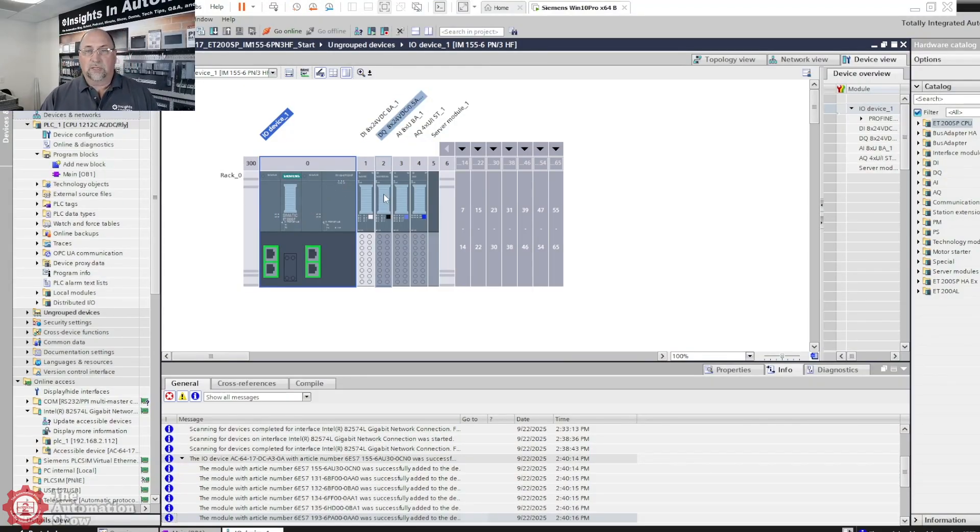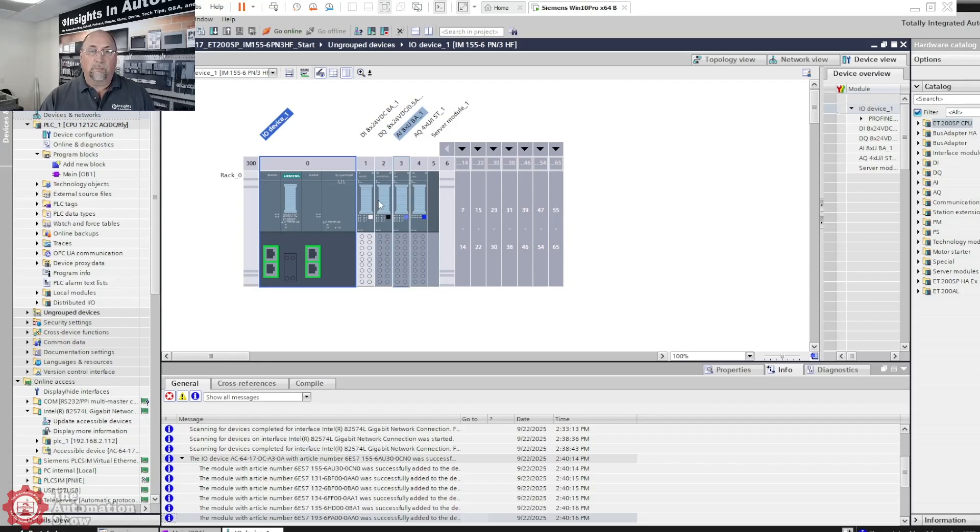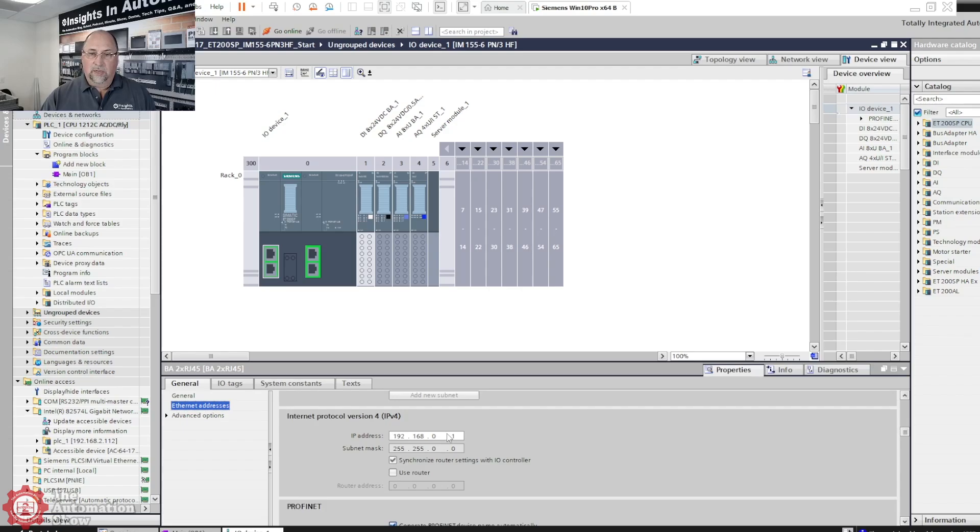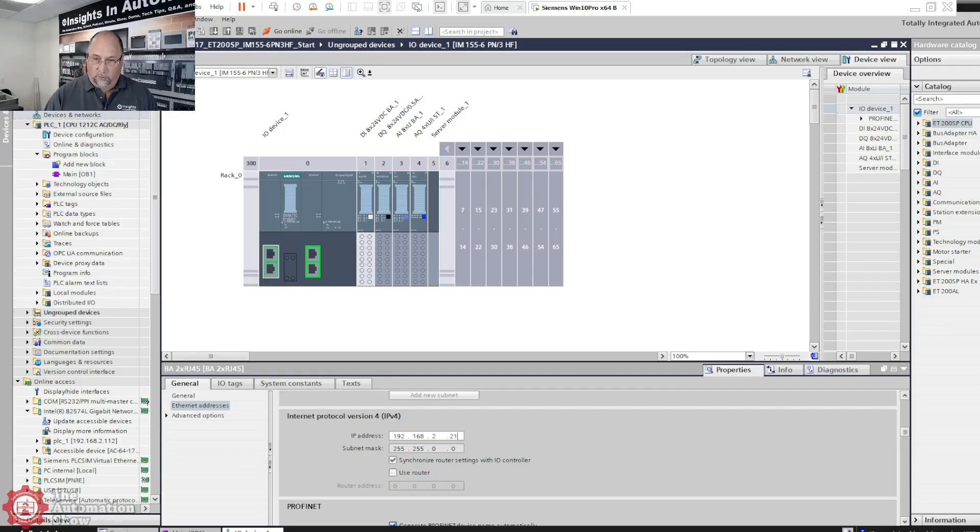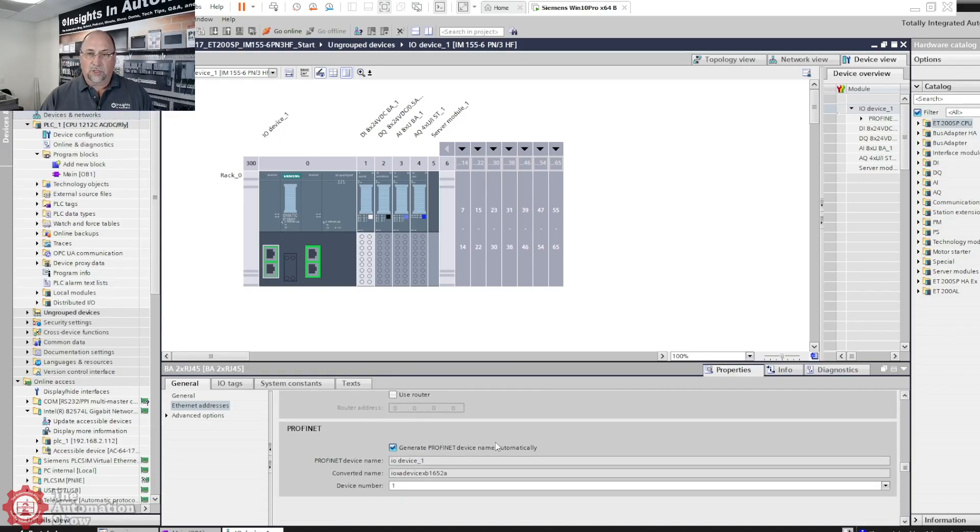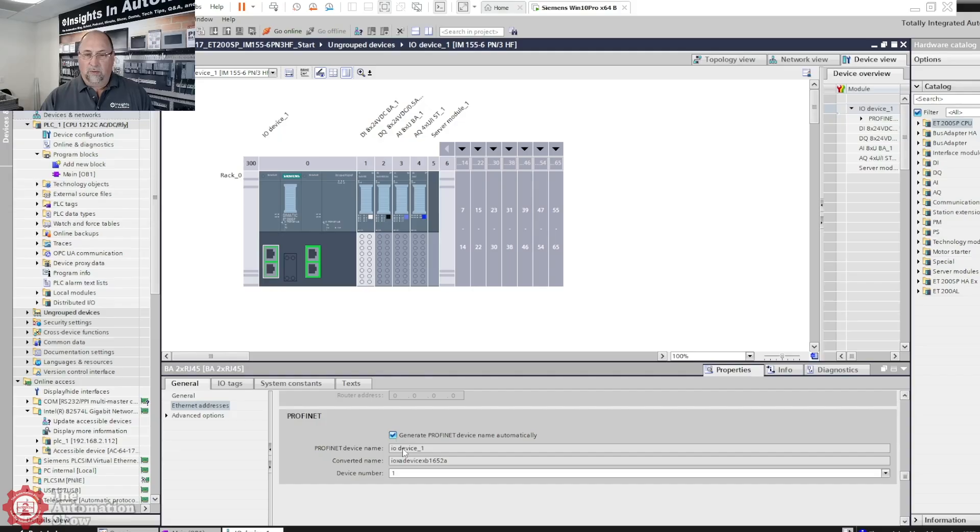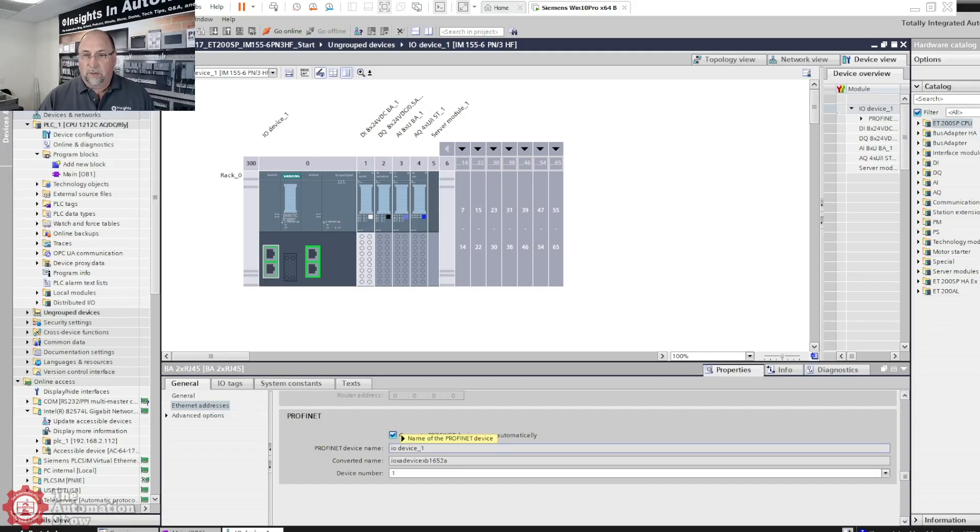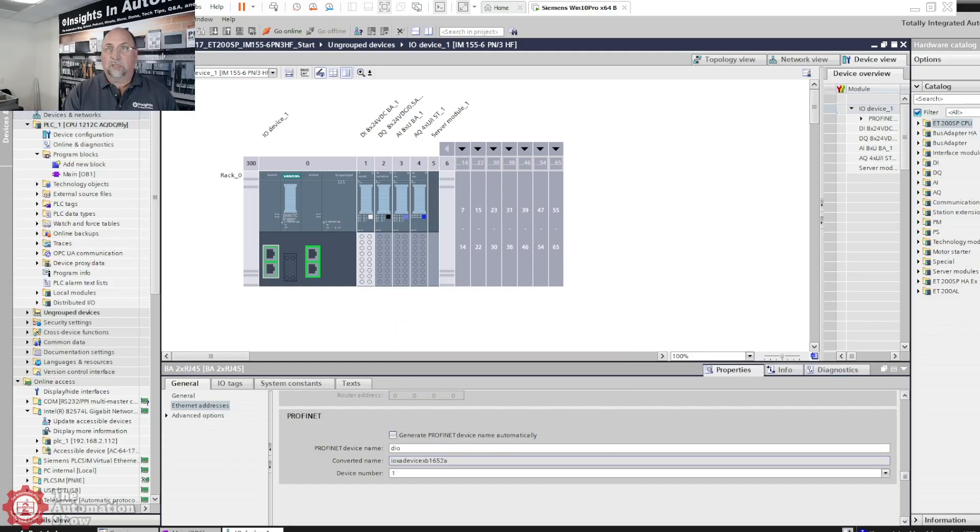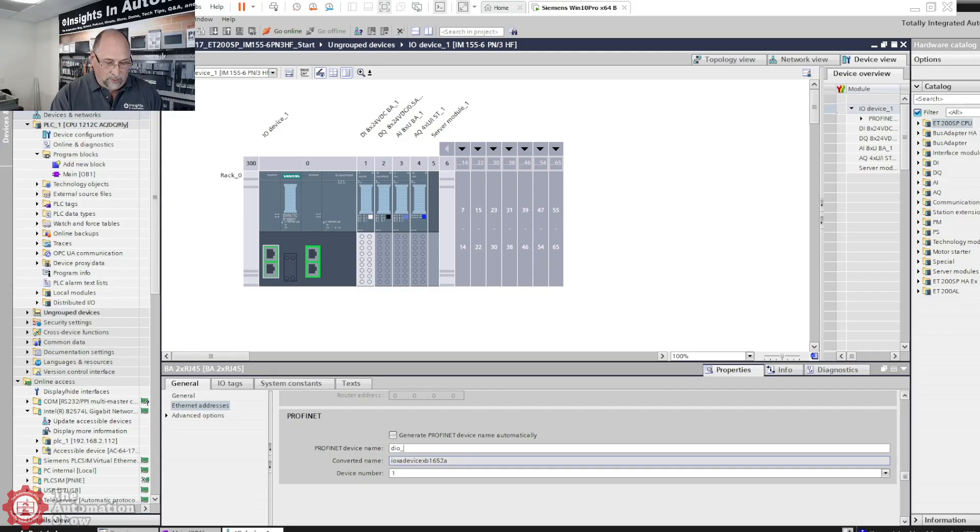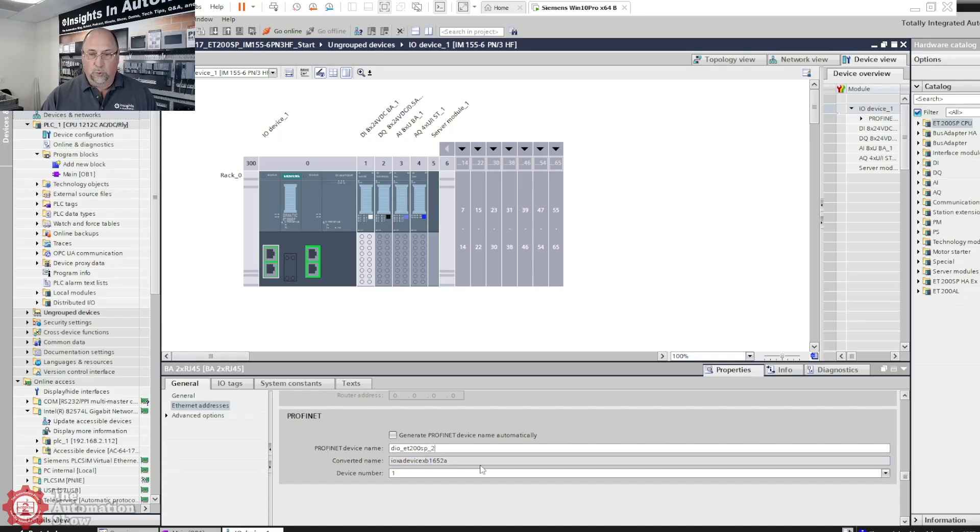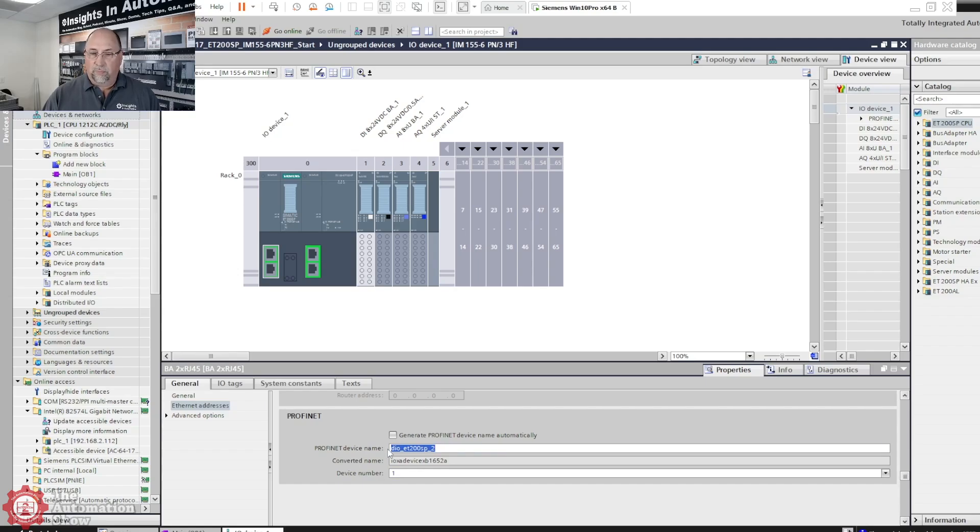Let me switch back over to the computer. We can see everything here, all the parts came right in, which is really cool. To make this work, first of all I'm going to have to give it an IP address. I want this to be 192.168.2. Yesterday was 213, so today will be 214. And I also have to give it a device name. This is the default. We're going to stay with the nomenclature we used so far in this series of videos, and that would be DIO-ET200SP. We're going to call this RAC2. So let me copy that. That Profinet name is very important. We'll talk about that in a minute.